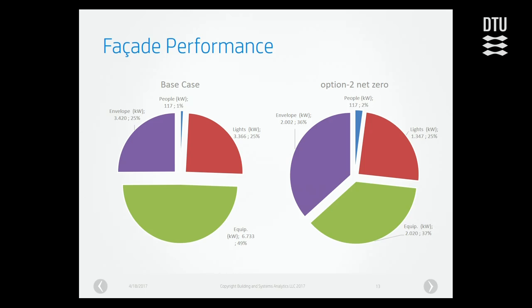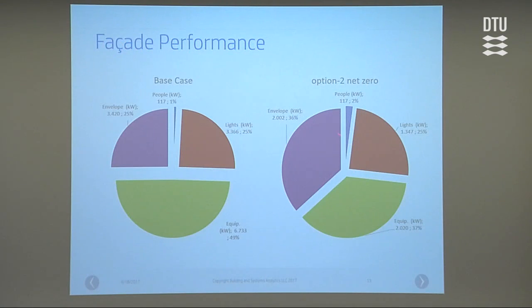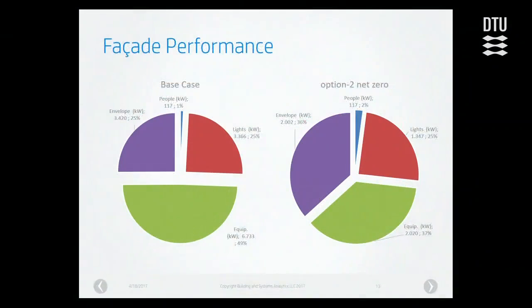But now what happens on this side, as soon as these loads go down, the lighting goes down and the equipment load goes down, this goes up to 36%. So the facade now is a big fluctuating load of 36% of the total building load, and it becomes critical to look at it because we've got to deal back as mechanical engineers to the architects and give them guidance over the type of glass.